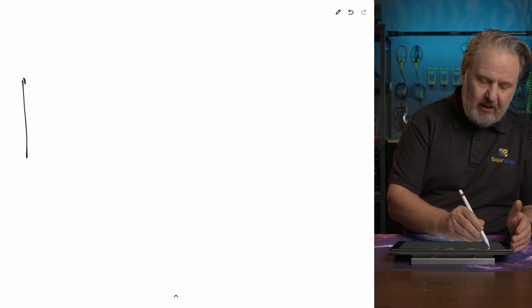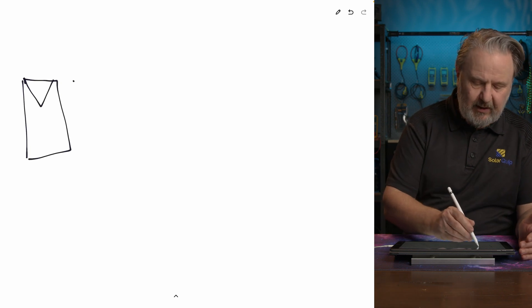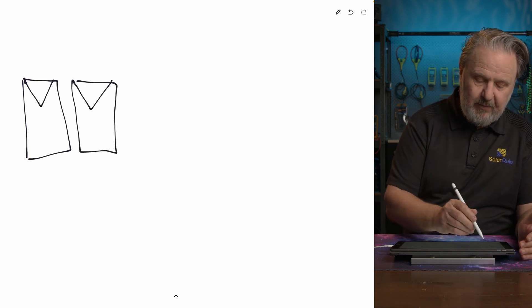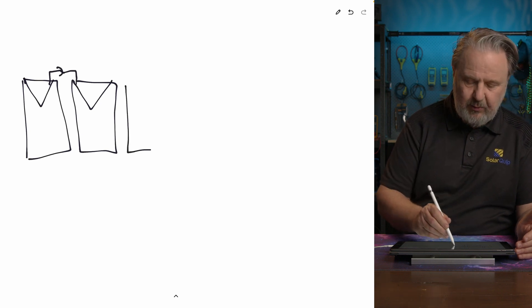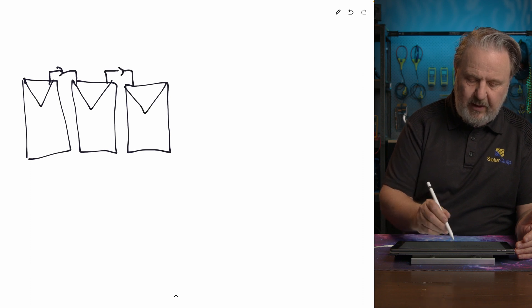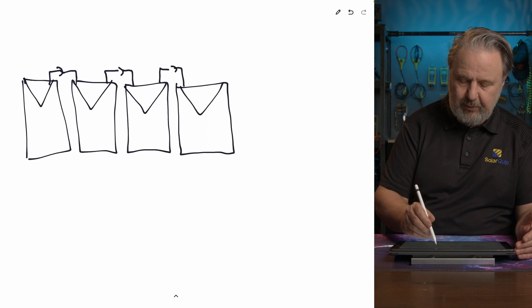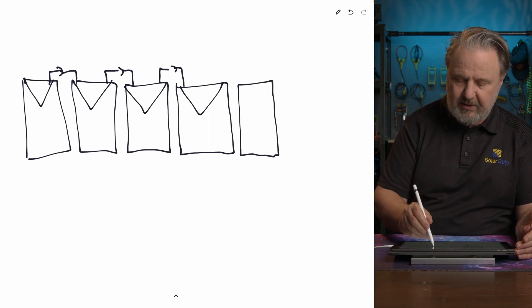Let's start by looking at how one of these systems is put together in a simple schematic. We've got a bunch of solar panels — that's the symbol for a solar panel. Solar panels on systems typically are connected in series with plugs and sockets, forming what's known as a string of solar panels. The positive of one connects to the negative of the next, and that builds up the voltage across the array. So the voltage is going up as we add more solar panels to the string.